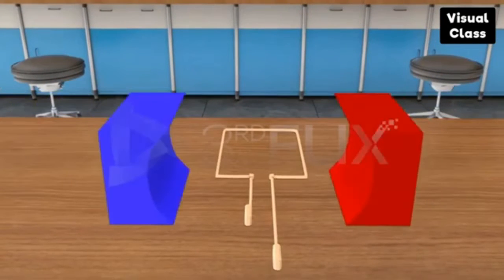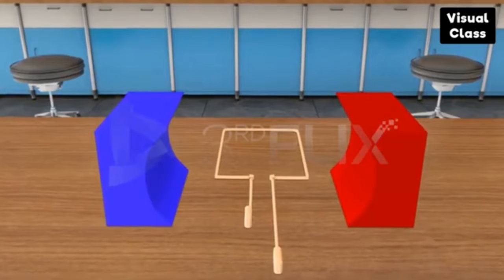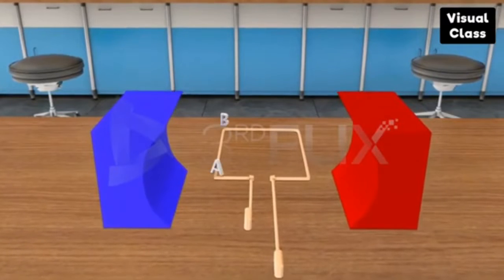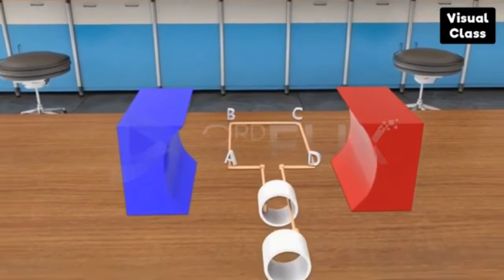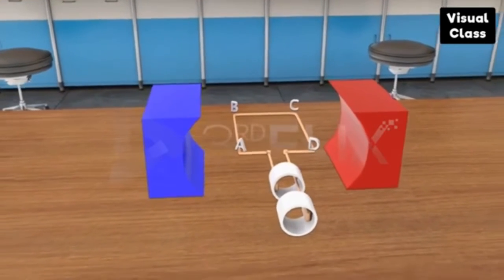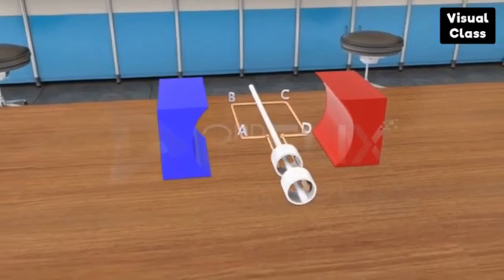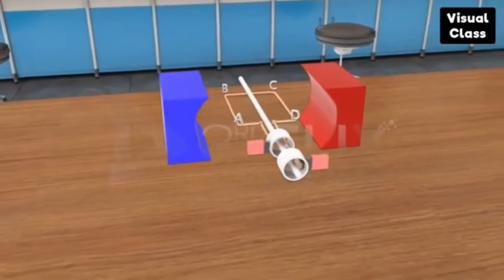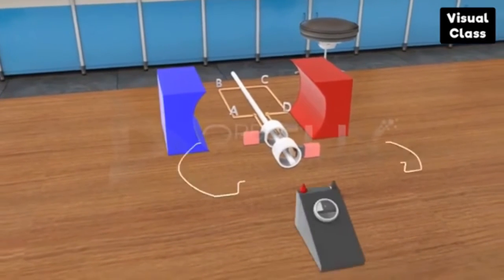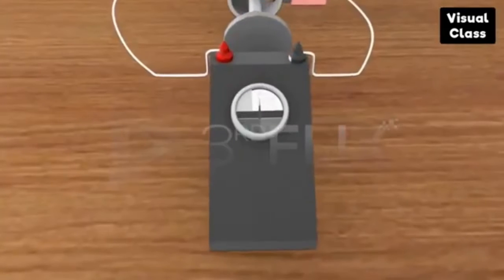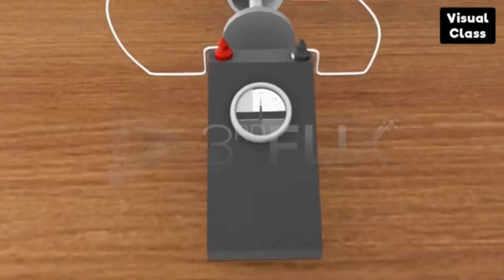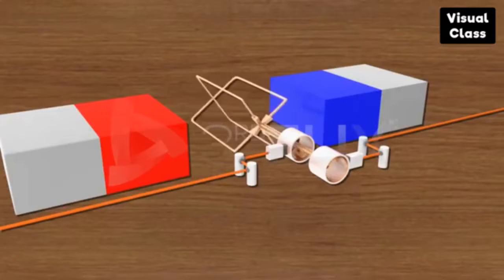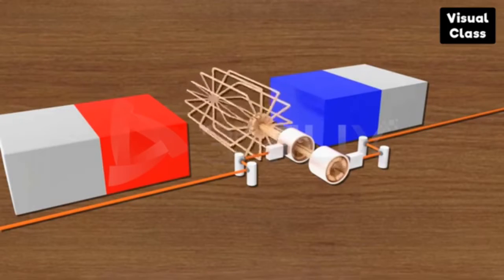The main parts of a motor are the wiring cover, motor casing, stator, rotor, bearings, and end bell. The rotor is the set of winding and magnetic core to which the motor shaft is attached. A commutator is used to reverse the direction of current in the rotor in order to maintain a repulsive force between the rotor and its stator poles.